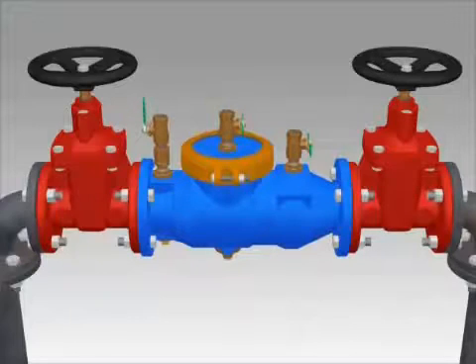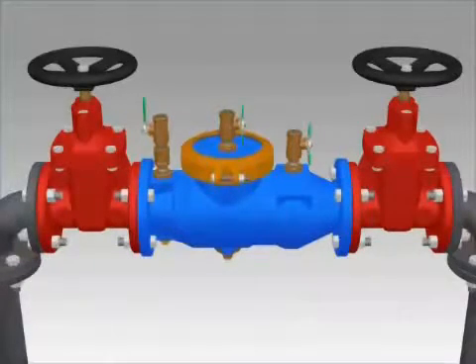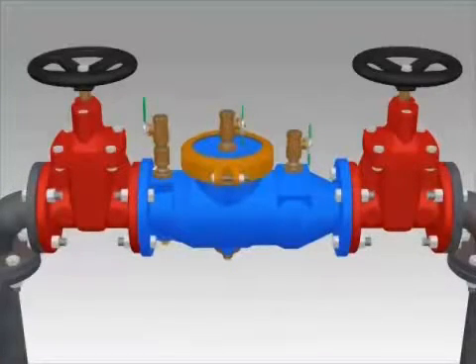Open the number 2, number 3, and number 4 test cocks to release the pressure from the valve. Leave the test cocks open during check removal and reinstallation.